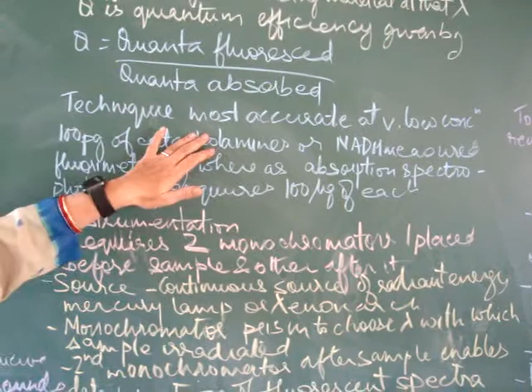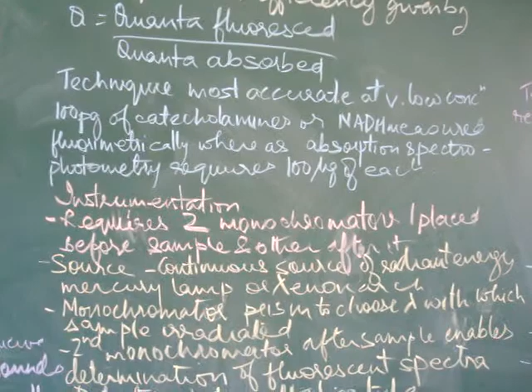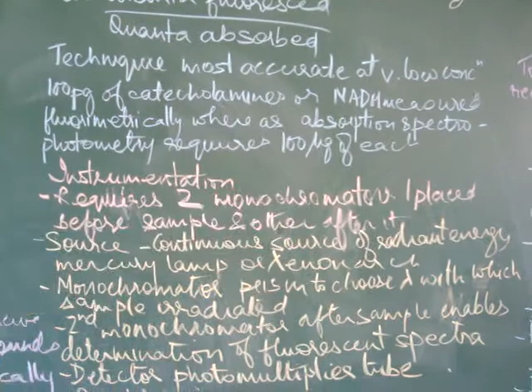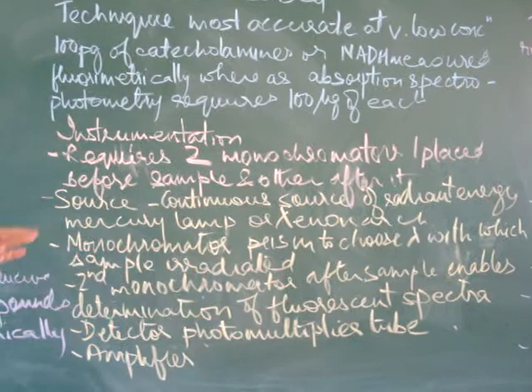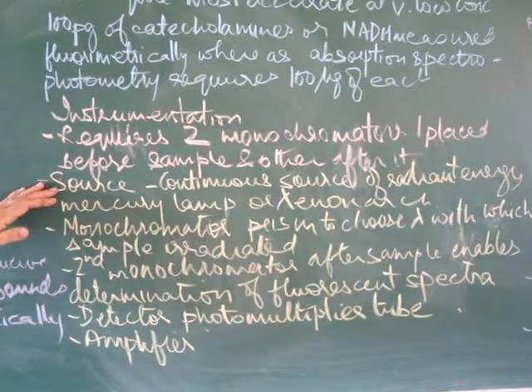Technique: most accurate at very low concentration. 100 picograms of NADH or catecholamines can be measured fluorimetrically, but for spectrophotometry we require 100 micrograms. So here very little quantities are required. Instrumentation: two monochromators are required, one before the sample and one after the sample. The source is a continuous radiant energy source, a mercury lamp or xenon arc.